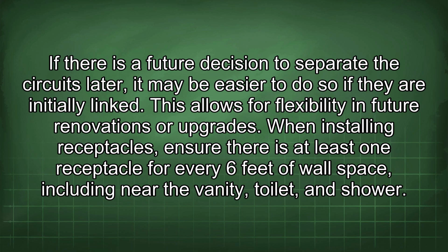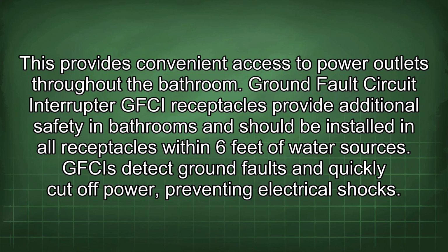When installing receptacles, ensure there is at least one receptacle for every 6 feet of wall space, including near the vanity, toilet, and shower. This provides convenient access to power outlets throughout the bathroom. Ground fault circuit interrupter (GFCI) receptacles provide additional safety in bathrooms and should be installed in all receptacles within 6 feet of water sources. GFCIs detect ground faults and quickly cut off power, preventing electrical shocks.